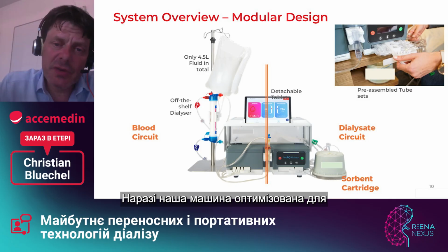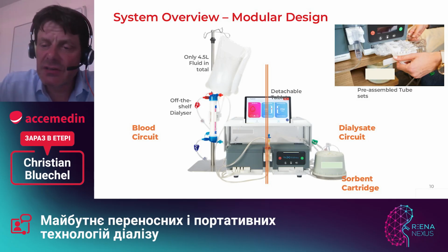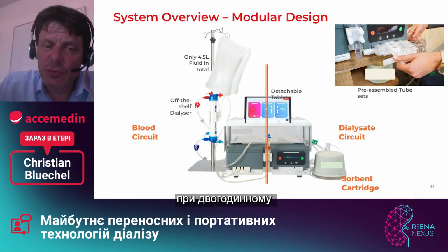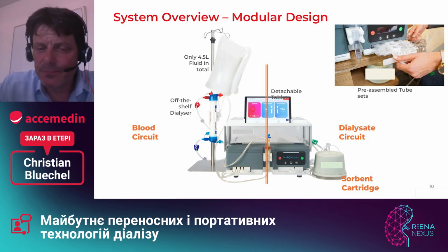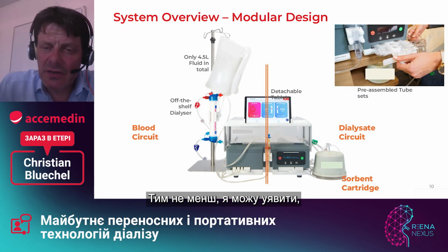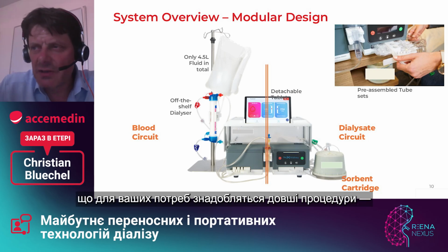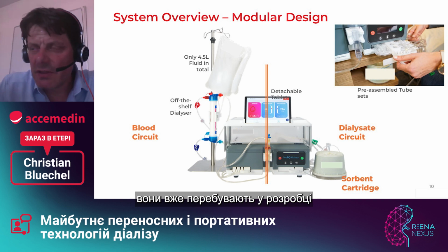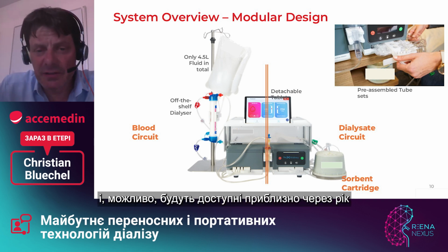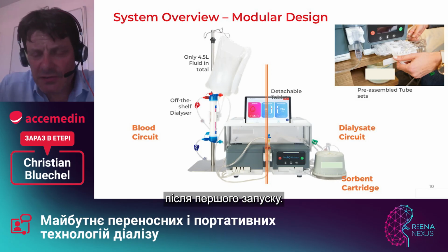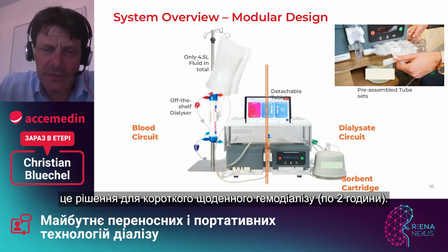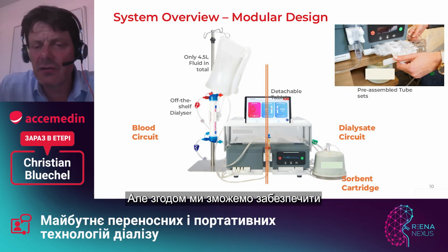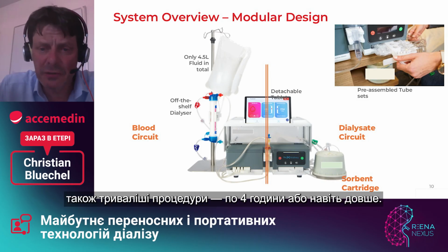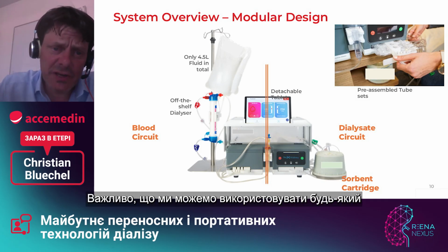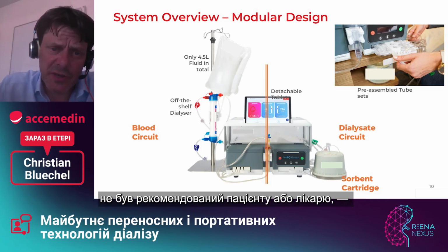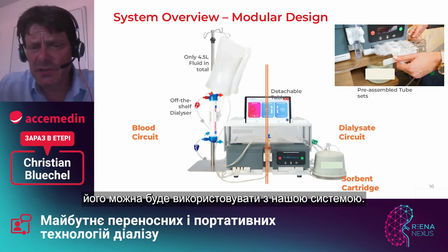Our machine currently is optimized for short daily hemodialysis, which means it's optimized for a treatment of 2 hours of dialysis per day. That said, I can imagine that in your type of applications, you will need longer therapies. That is in the pipeline and will come maybe 1 year later. After the first product that we bring on the market will be the short daily hemodialysis for 2 hours, but then we can also have longer treatments of 4 hours or even longer. Importantly, also we can use any off-the-shelf dialyzer, so whatever the patient or the physician prefers can be used for this kind of treatment.